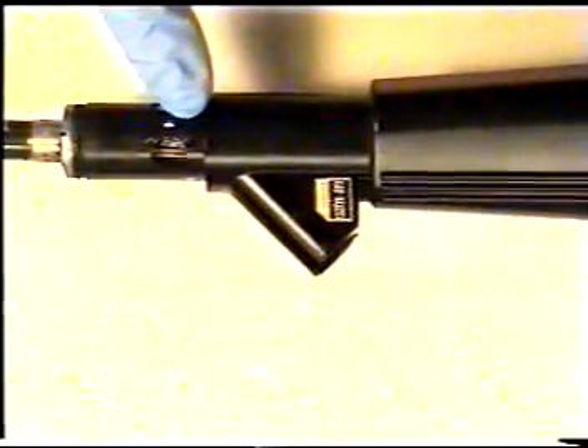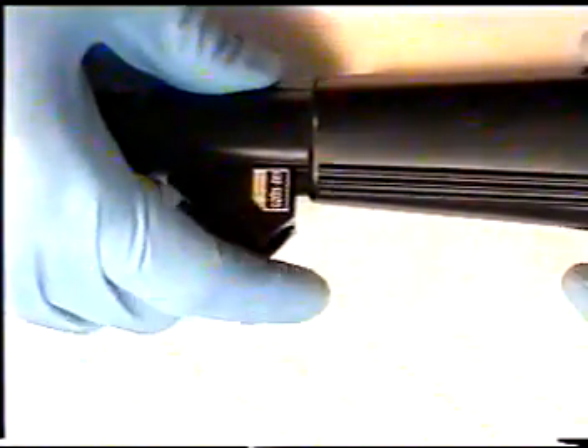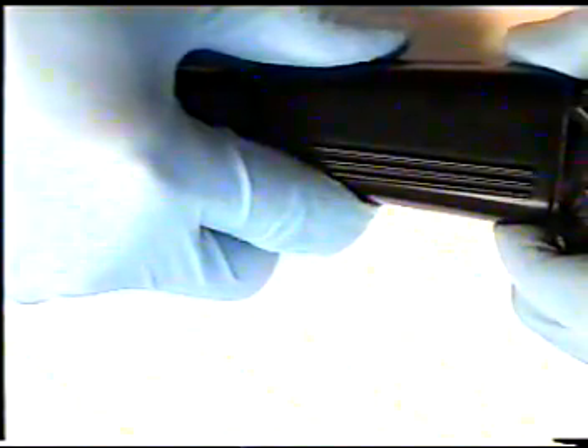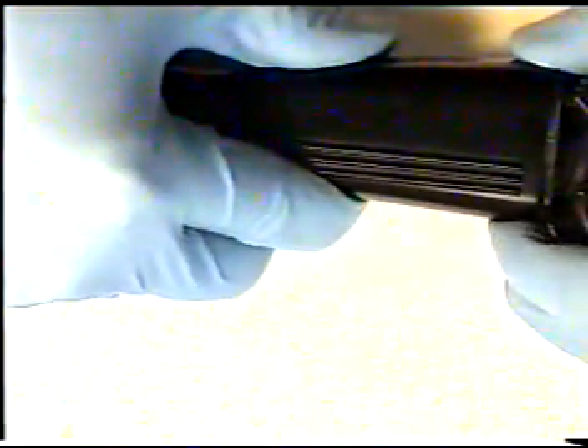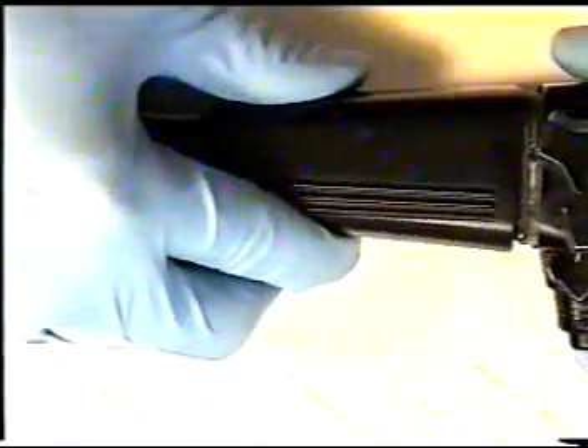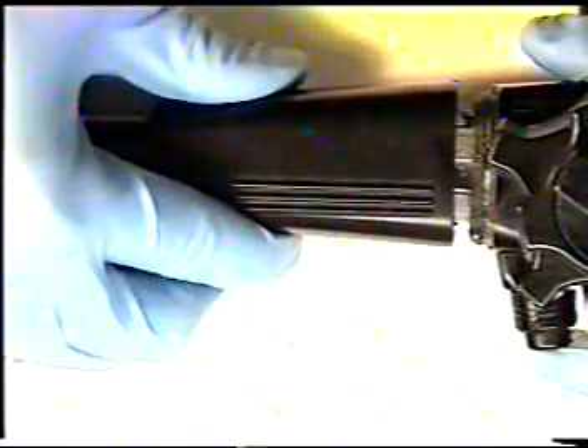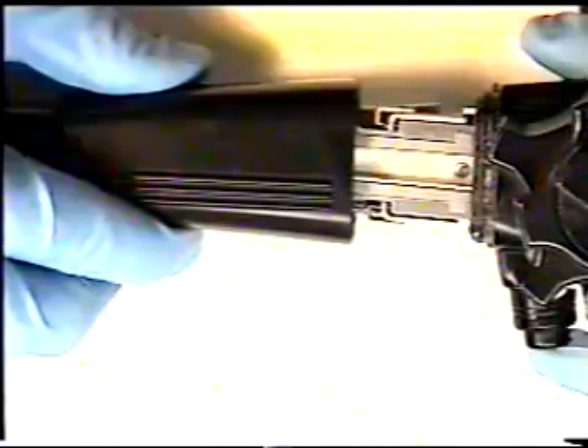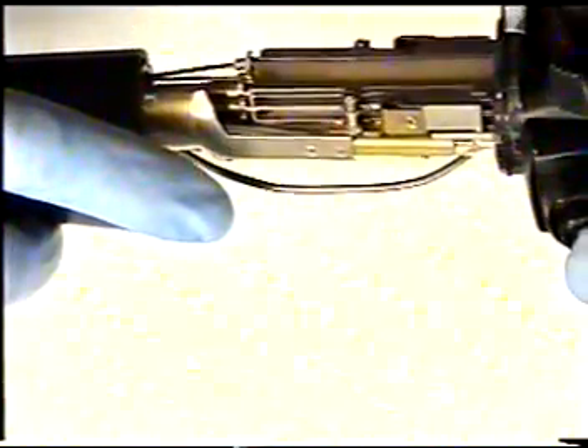Once the retaining ring and biopsy port have been removed, we can now pull down the control body section. Carefully grasp the control body section midway, pulling down towards the insertion tube. Be extremely careful when removing the body cover, so as not to pinch the light bundle and/or video cable or image guide bundle underneath. This will cause permanent and serious damage.